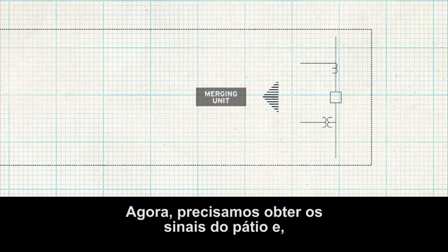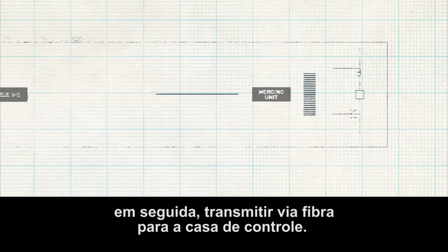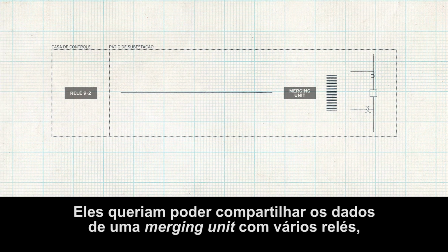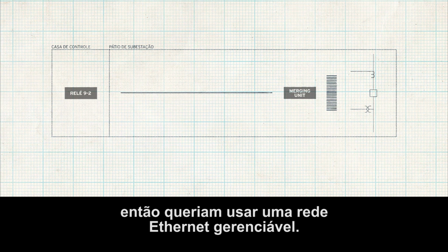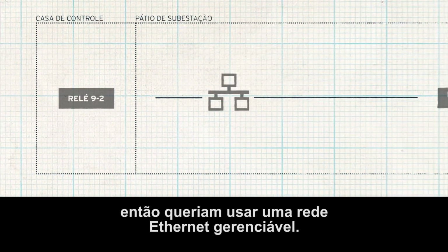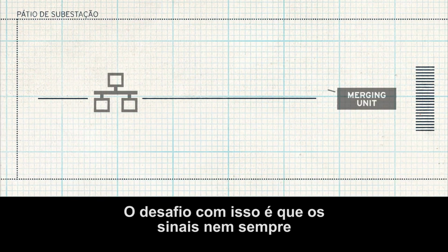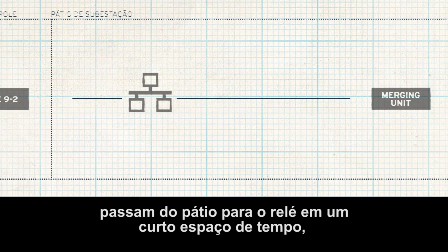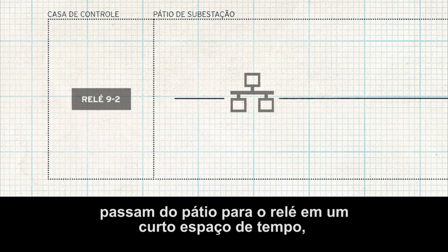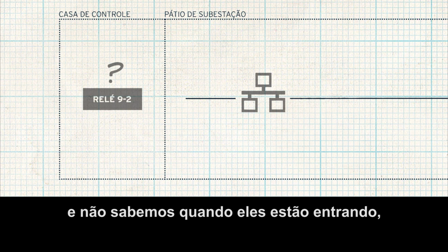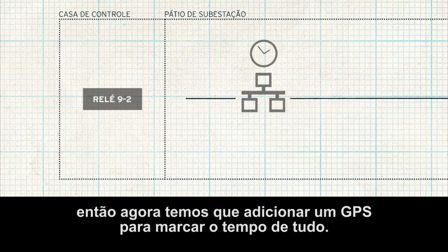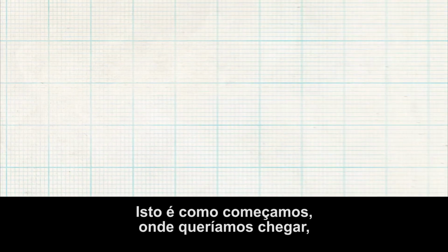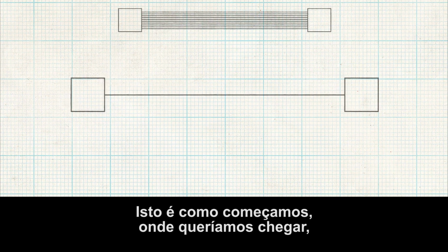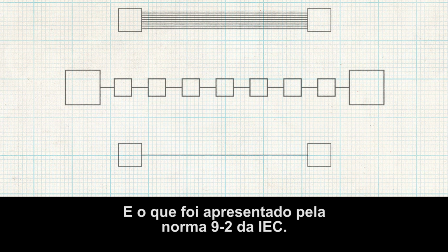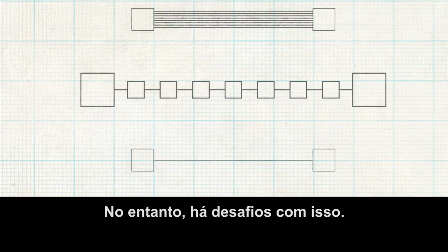Now we need to get the signals from the yard over fiber to the control house. They wanted to be able to share the data from one merging unit with multiple relays, so they came up with using a switched Ethernet network. The challenge with that is the signals don't always get from the yard to the relay in a short time, and we don't know when they're coming in, so now we have to add a clock to time tag everything. So there's where we started, there's where we wanted to go, and the IEC committee came up with the 9-2 standard. However, there are challenges with this.